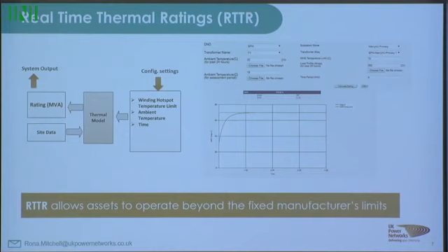What we do is take the winding hotspot temperature limits from all the different transformers, the historical ambient temperature, with some site-specific data, and put it into a thermal model with some clever data science that outputs a more dynamic, realistic rating for the transformer that planners can use to plan their work.